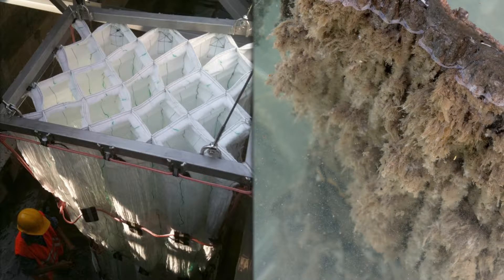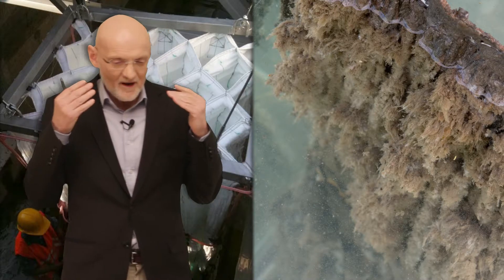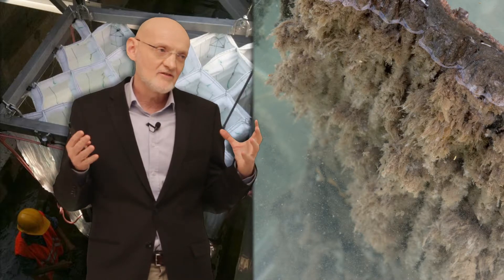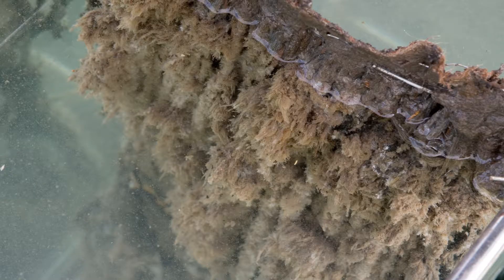On the next slide you can see a typical bio module — you can make out a construction worker in the lower left corner for scale — and the biofilm that grows on this media. It's important to note there is a lot of biomass: more than 12 kilos per cubic meter. It is also very fluffy. And notice that the water is relatively clear, because almost all the biomass is attached and very little is swimming in suspension. This is why the water is relatively clear.